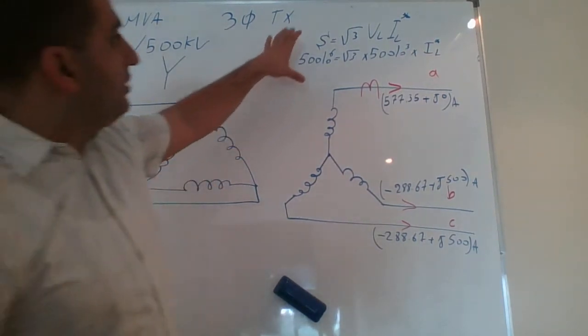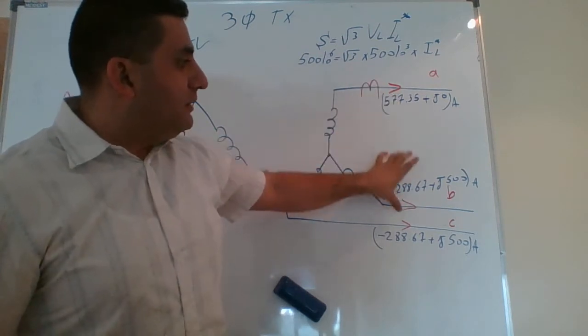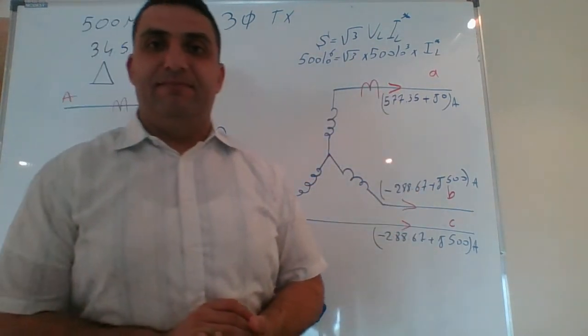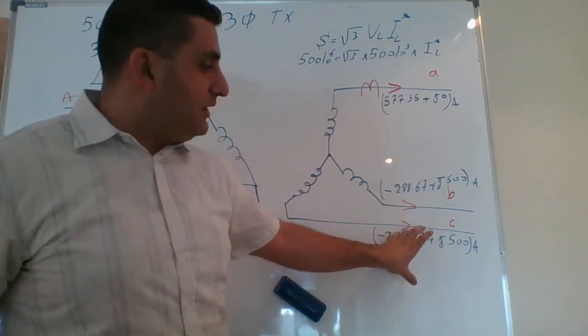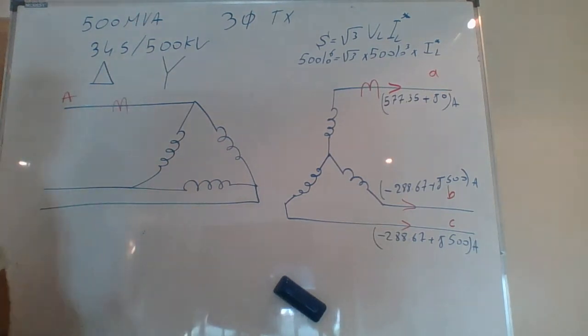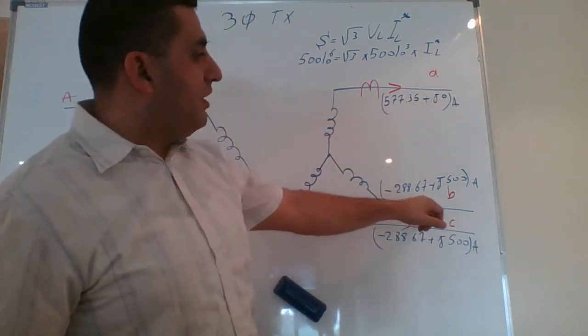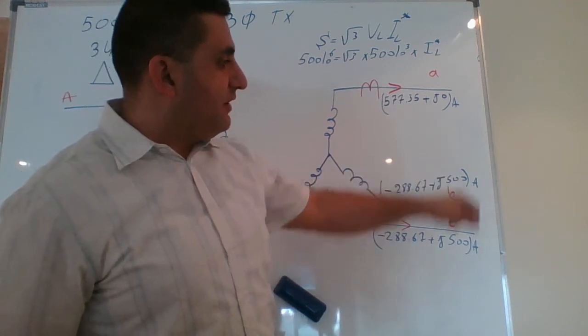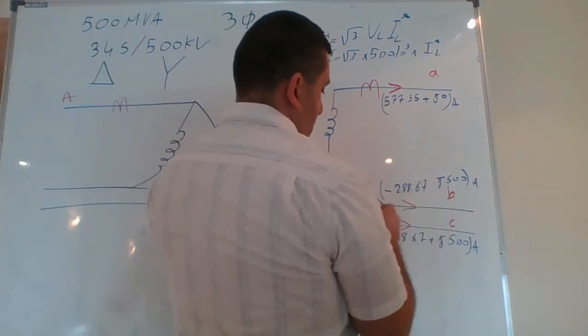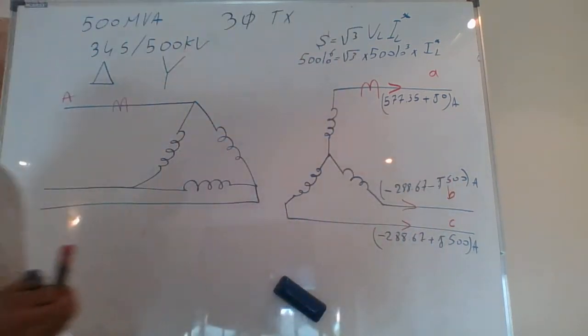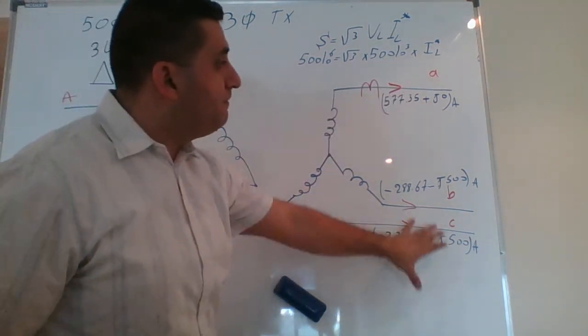After calculation, using phase A as reference with angle zero, I add minus 120 degrees for phase B and plus 120 degrees for phase C. The results are: Ia = 577.35 + j0; Ib = −288.67 − j500; Ic = −288.67 + j500. Now I go back to calculate the current on the primary delta side.